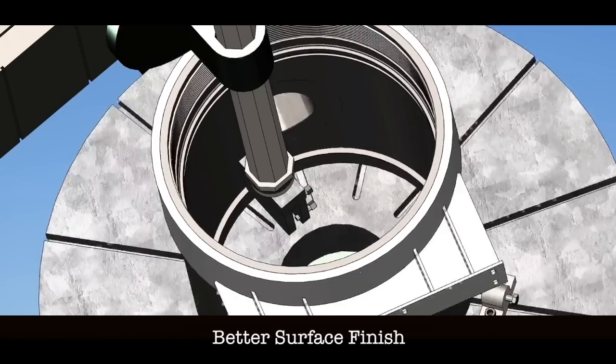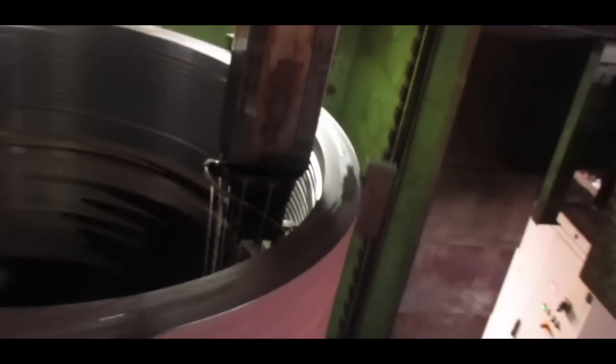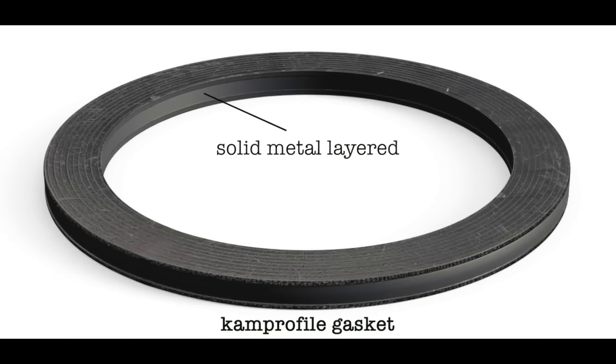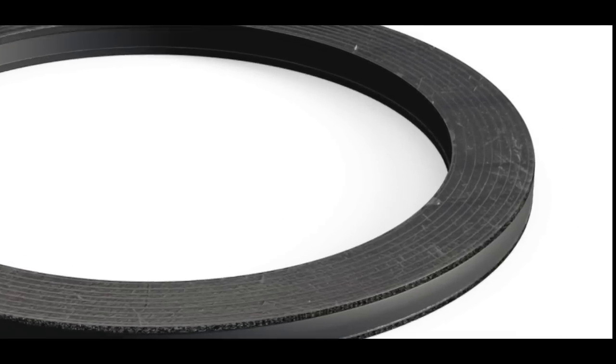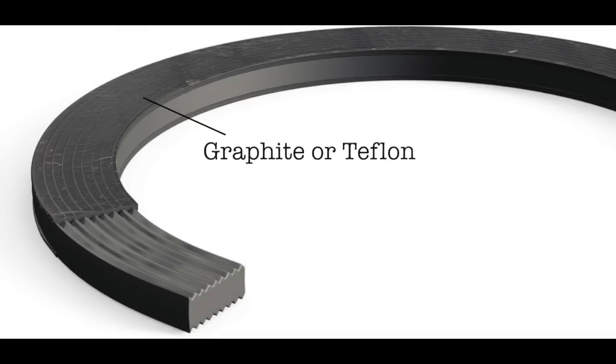Our channel barrel is separately machined on a VTL to give the required finish for a cam profile gasket. Being a grooved metal gasket, the cam profile gasket must be uniformly loaded.